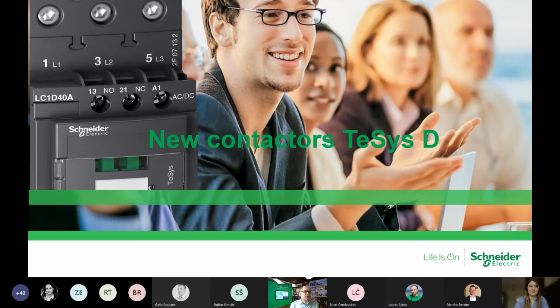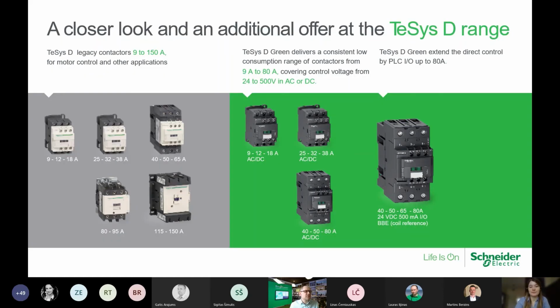The new product is called TeSys D Green. Compared to our existing TeSys D range — a good range, many years in the market and still continuing, from 9 amps up to 150 amps in about 5 types — this new Green range has an electronically controlled coil, and we only go up to 80 amps in 3 sizes. So we've reduced the sizes significantly. The main advantage, which I'll show later, is that up to 80 amps we can directly control these new contactors from a PLC.